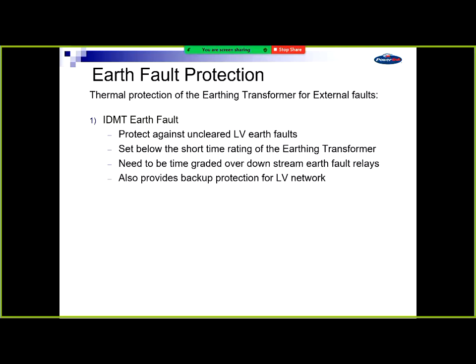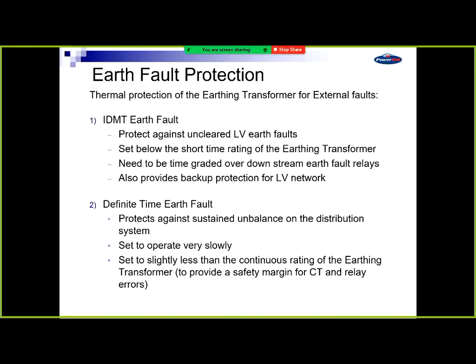If that fault hadn't been cleared, there would have been a lot more plant tripping across Queensland and the eastern seaboard. So having this low voltage backup, it's not in your mandate, but it does provide a degree of backup that is easy to do, secure, and gives you a little bit extra for nothing. It's basically how I say we do it. It's not intended to work, but it can. And it's not the only time that sort of thing has happened over the years.